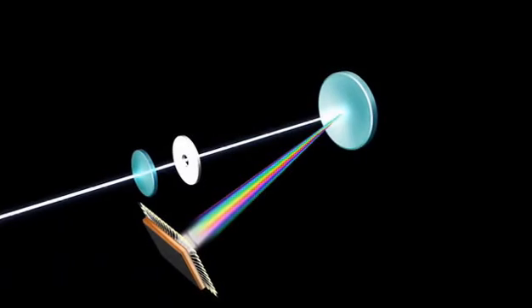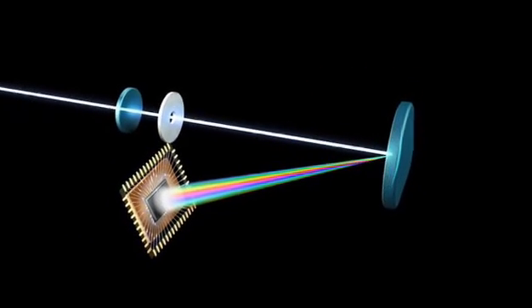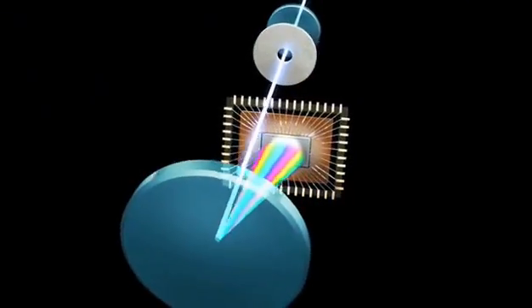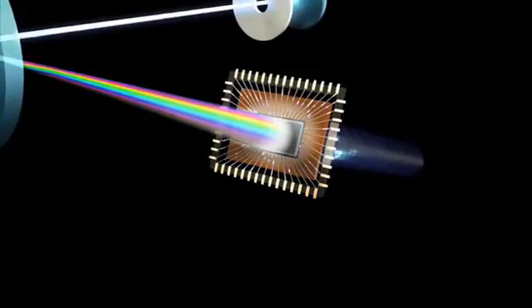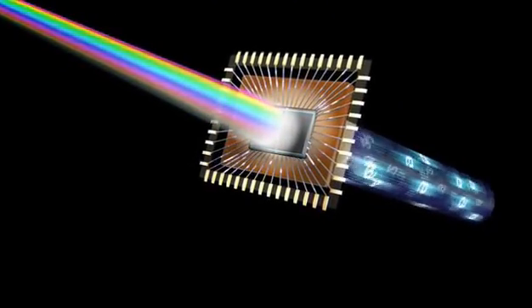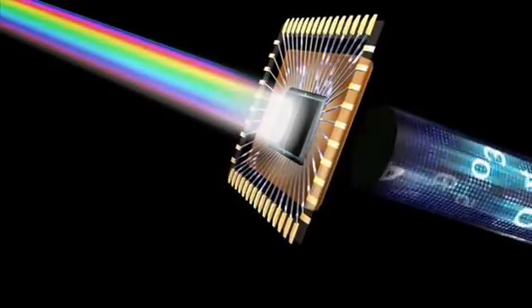This high-precision, multi-channel system optics consists of a mechanical slit, an aberration-corrected grating and the diode-array detector. Encased in a rugged quartz ceramic body, it is permanently adjusted, fixed and insensitive to external influences. This design ensures extremely accurate and highly reproducible results.